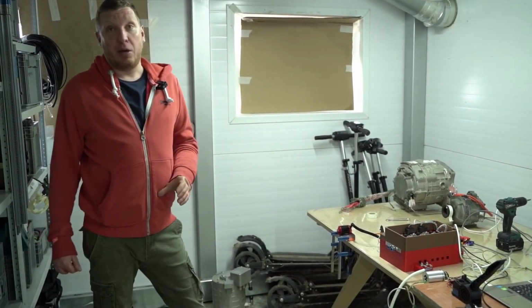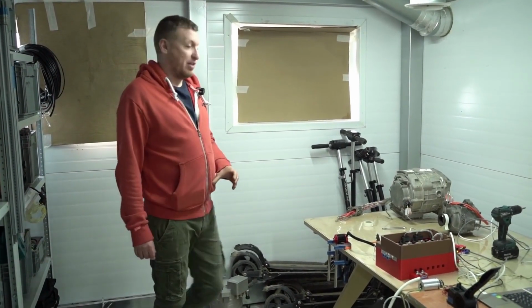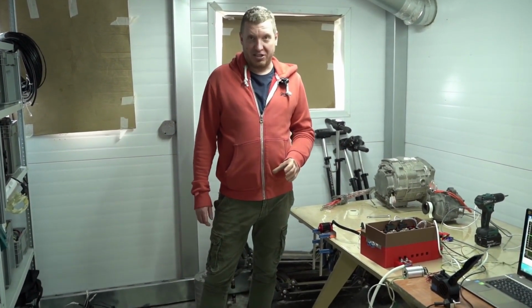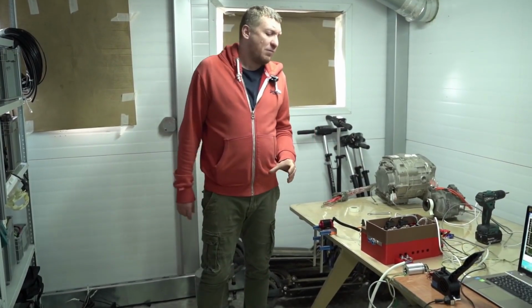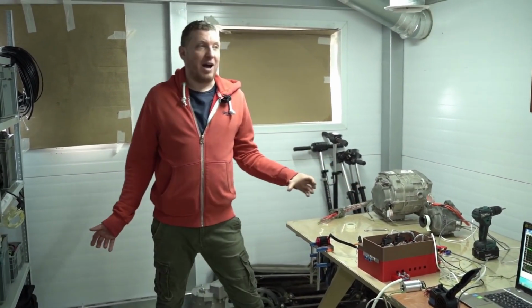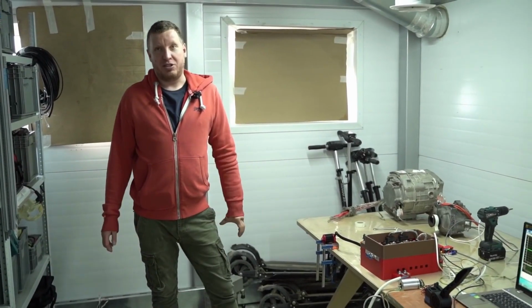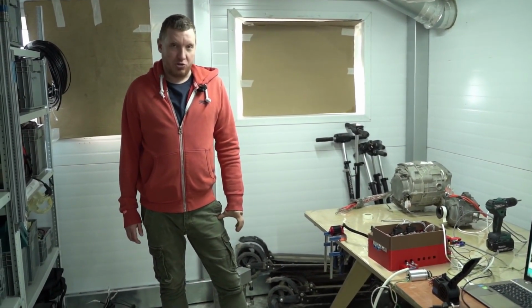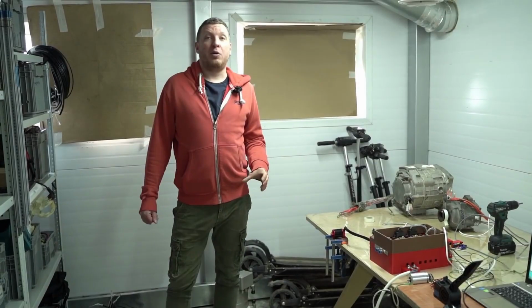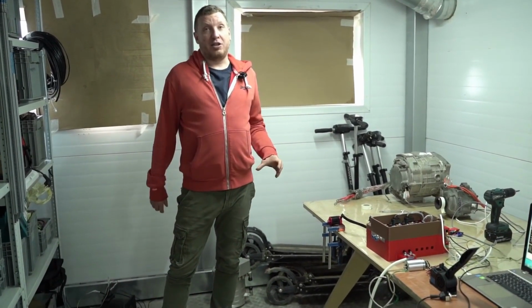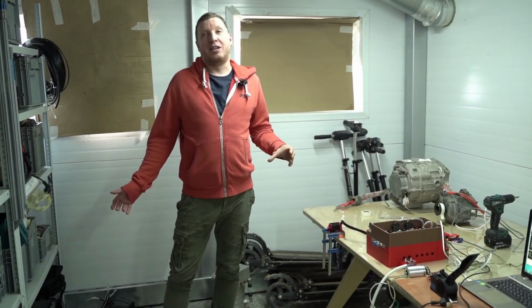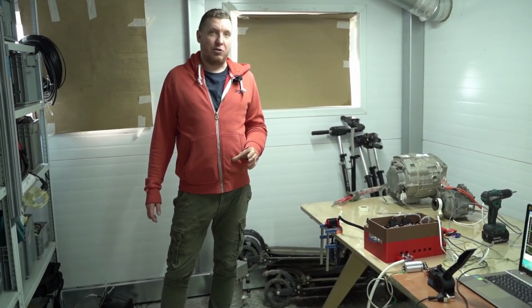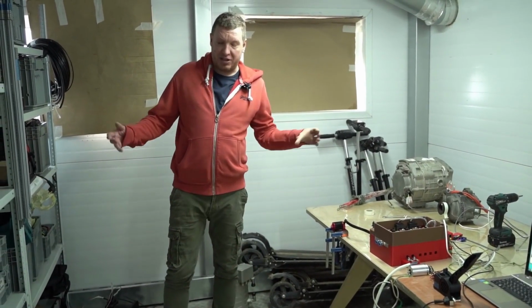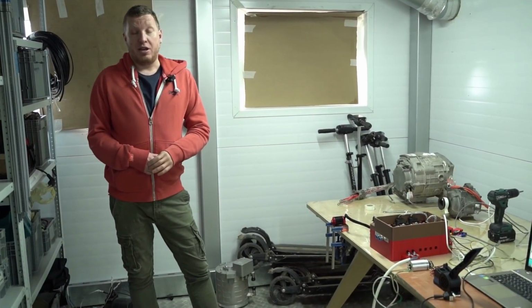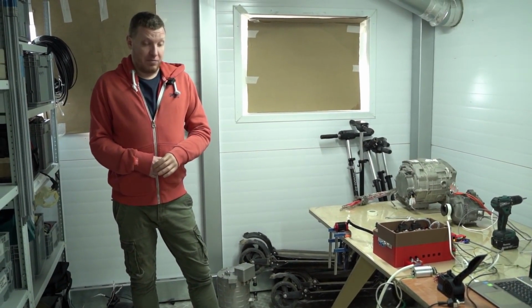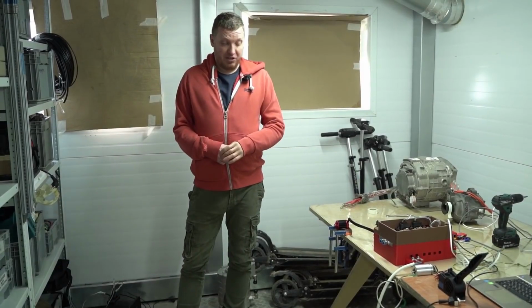We'll see, once we set up the test bench and everything is running under load under serious conditions, about 60 kilowatts, then it'll be proper. But that will depend more on the power module, if it's cooled properly everything should be fine. Maybe we'll need to tweak the control system a bit, but for that we'll need to actually set up 60 kilowatts. There's no way you'll find enough Variacs for that, you need something around 100 kVA. We'll have to assemble a battery, at least with a small capacity but capable of decent current, and a load test bench. So I really liked it, and I think everything will turn out great.